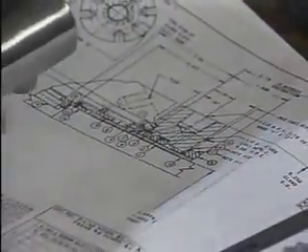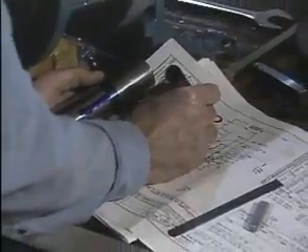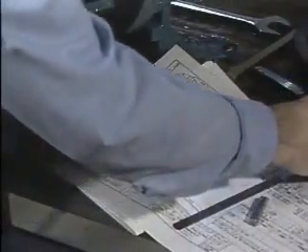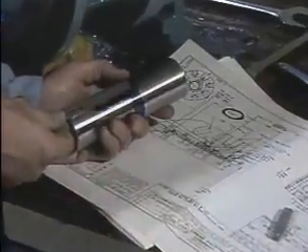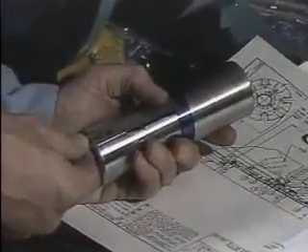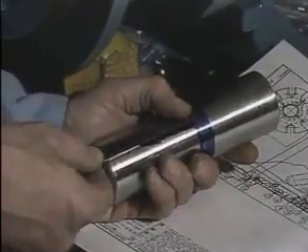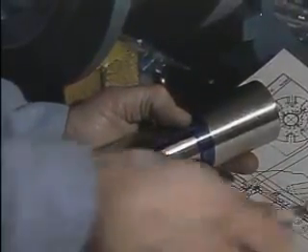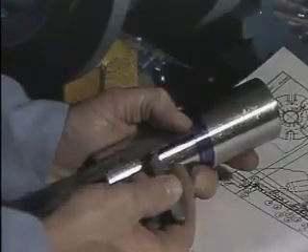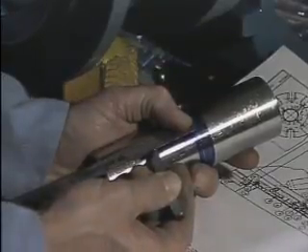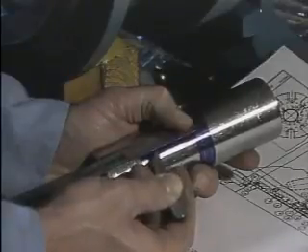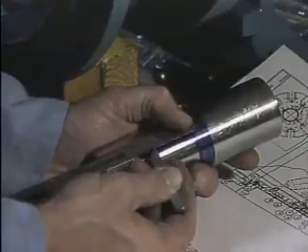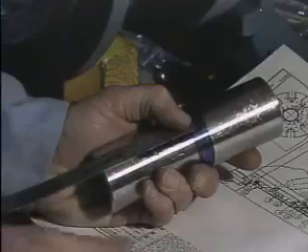Next, the seal manufacturer's installation instructions are checked to determine where the collar should be mounted on the shaft sleeve. The position of the collar is determined by using a measurement that's often called the location dimension. The location dimension is used to measure along the sleeve from the line marking the edge of the stuffing box. At that point, a second line is scribed in the bluing. This line serves as the reference line that helps to position the collar properly when the new seal's rotating ring is installed.